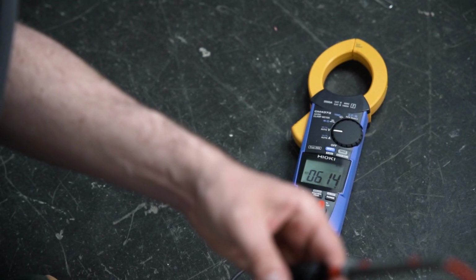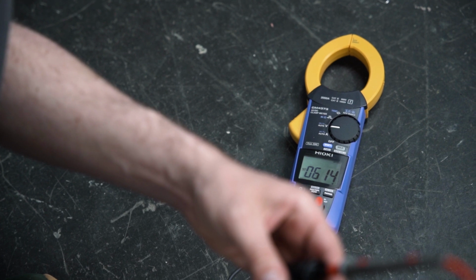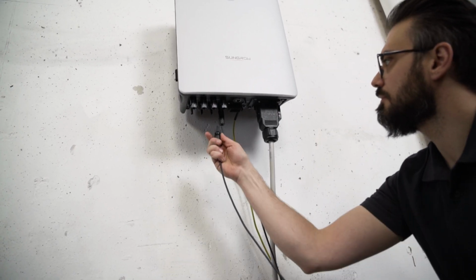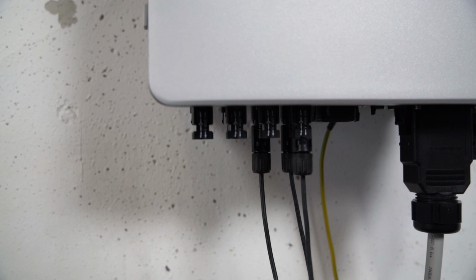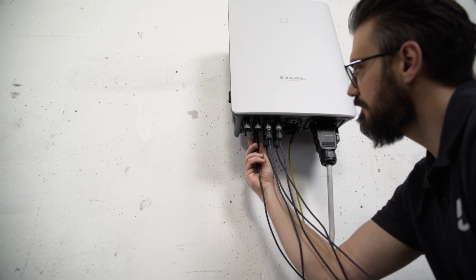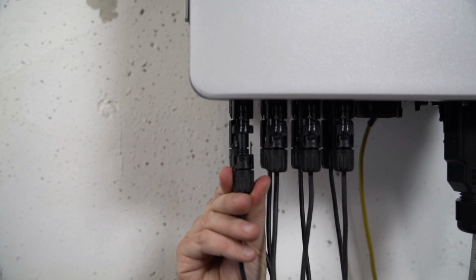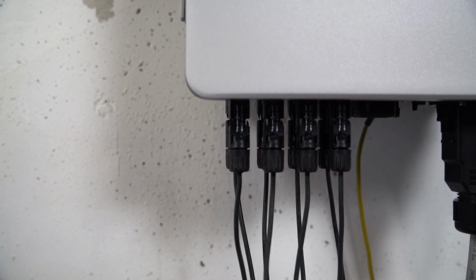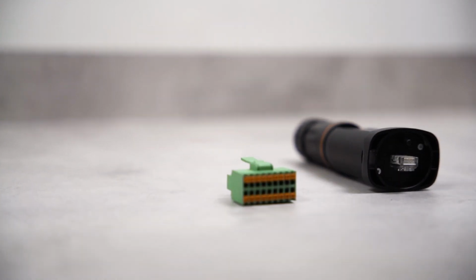Screw it, and that's it. Check again that the polarity corresponds to the imprint. The finished plugs only fit to the appropriate connections. The amount of DC inputs varies depending on the power range of the inverter. In the next step, we will set up the communication port.